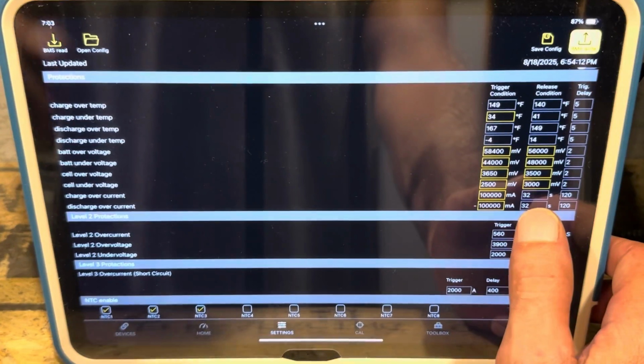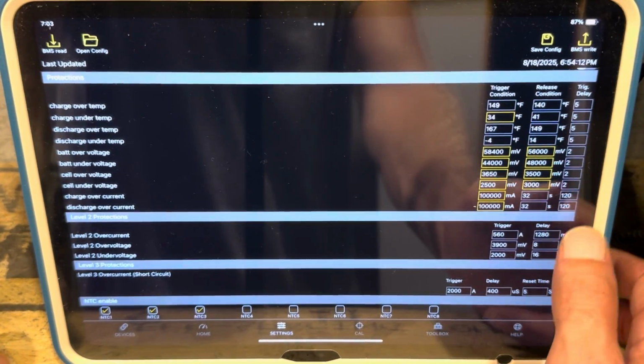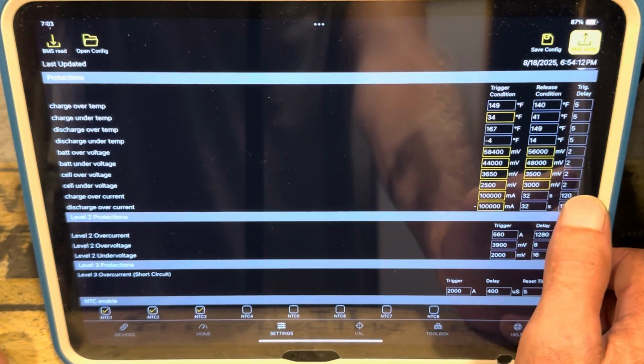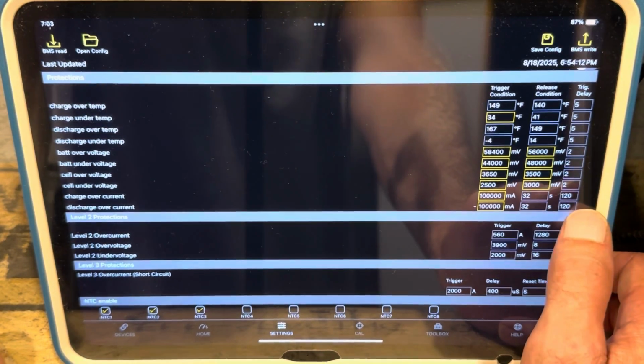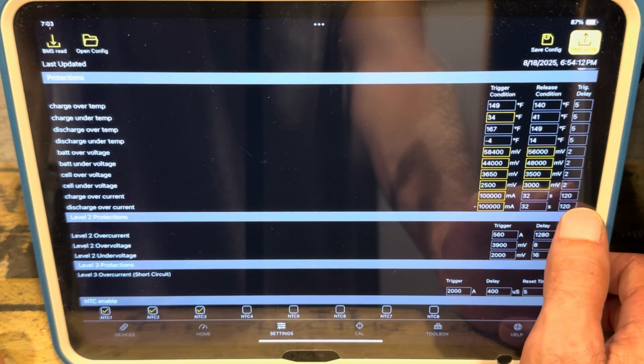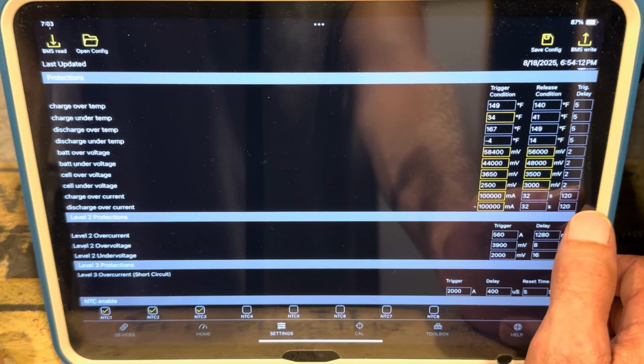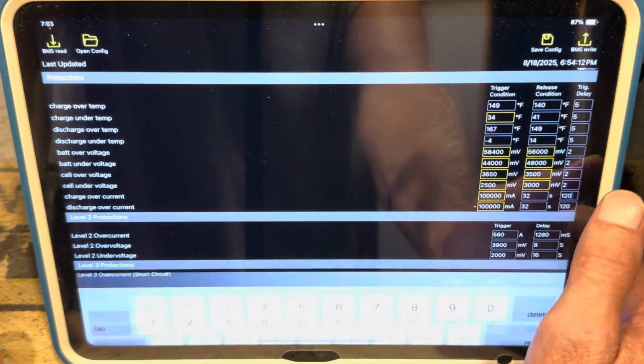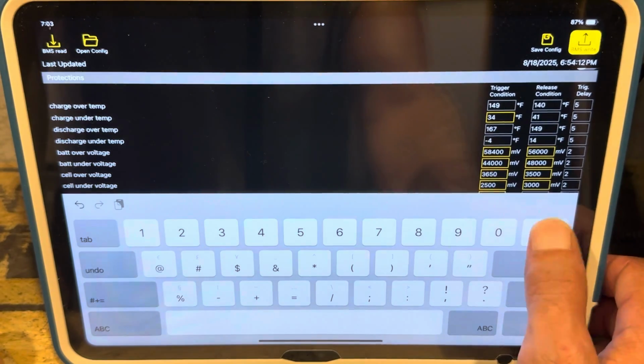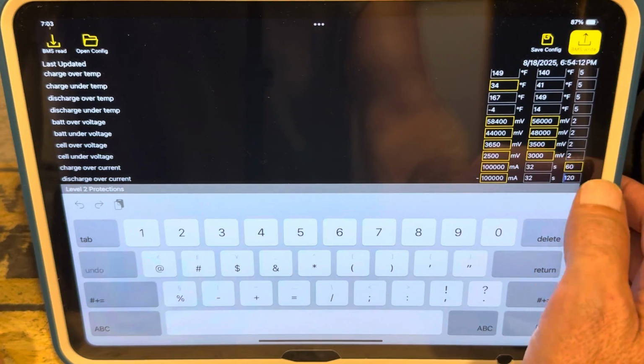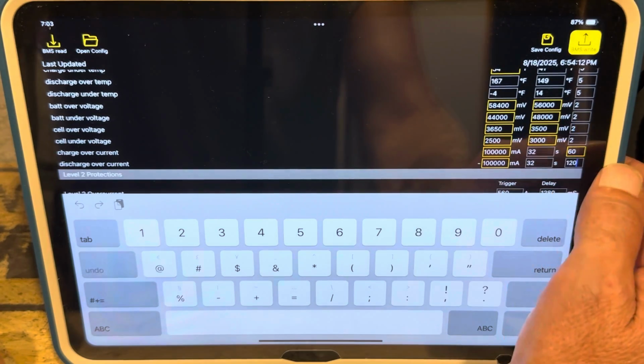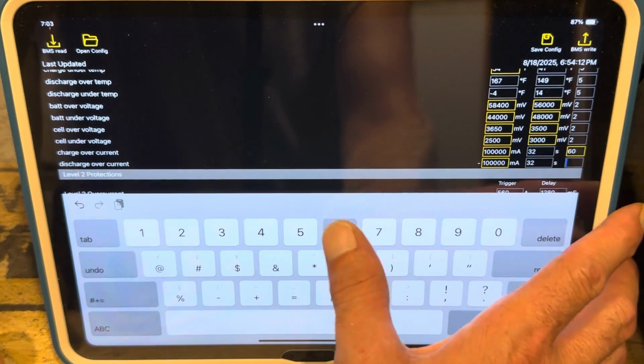And for the delay, that's the release condition - it's got a 2-minute delay at 100 amps. If you're going to slam the battery at 100 amps or have big surges on a single battery, 120 seconds is okay. I prefer to be a little more conservative - it'll handle that current no problem, but I'm just going to put that down to 60 seconds, which is a little better. No big deal - we're only at 100 amps, but the BMS can handle 100 amps quite easily. Just for the sake of changing, let's put it at 60 seconds.